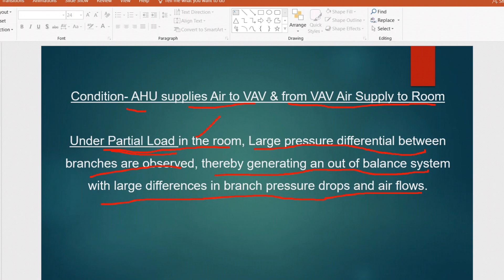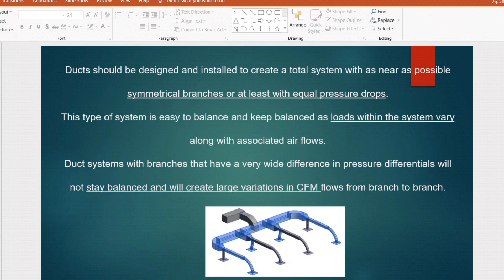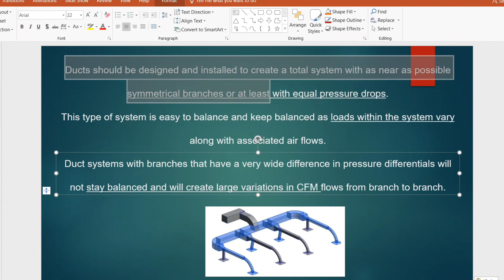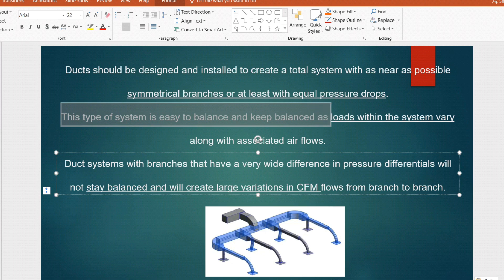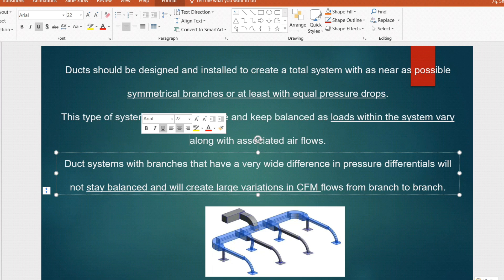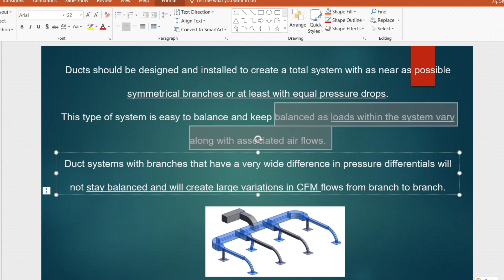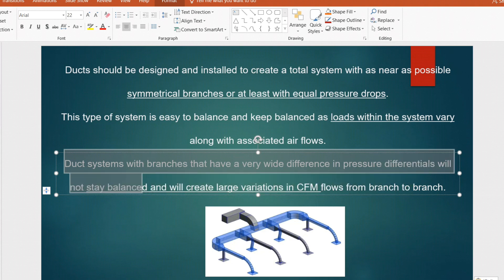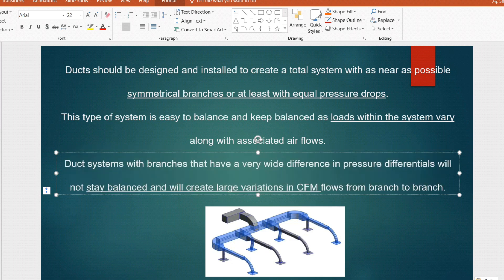For every project we do proper air balancing at the end as part of commissioning. From a designer's point of view, the system should be designed and installed to create a total system with as near as possible symmetrical branches, or at least with equal pressure drop. This type of system is easy to balance and keep balanced as loads within the system vary along with the associated air flow. Duct systems with branches that have very wide pressure differentials will not stay balanced and will create large variation in CFM flow from branch to branch.